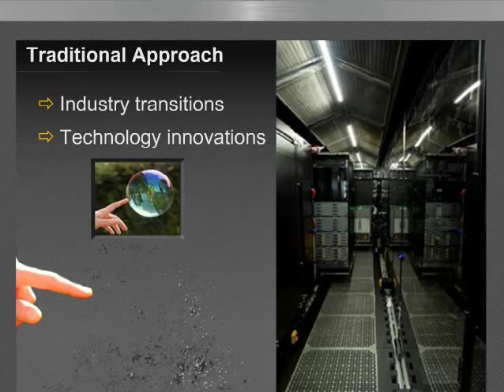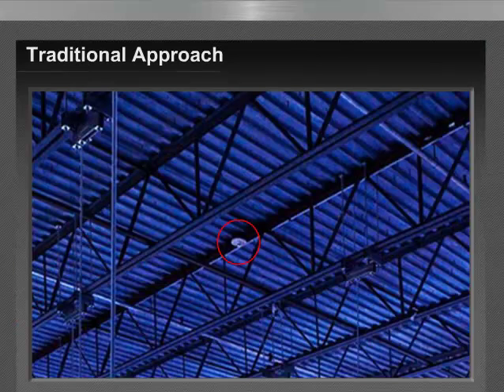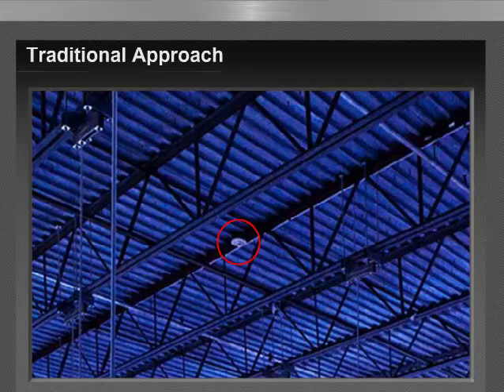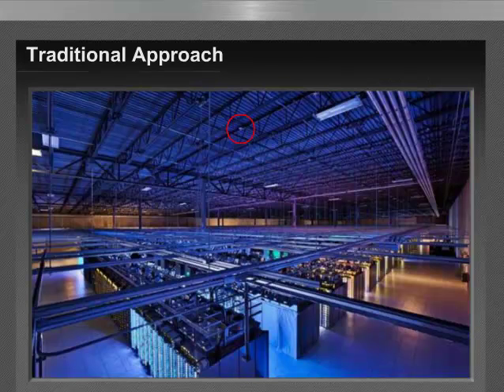So here we have an example of a situation we were discussing in the previous slide, using a traditional detector placed on a ceiling. While this appears to be a fairly ordinary and acceptable use of the detector, when we look at the application, we can see that in the actual facility, in the space that it's monitoring, there's a performance gap that will be evident. The performance gap is due to the environment, which may include airflow patterns, velocity, circulation. In addition, the high ceilings and likelihood of stratification will further add to the impediment of smoke. And in general, the effectiveness of the installation will not likely meet the performance expectations of the owner.